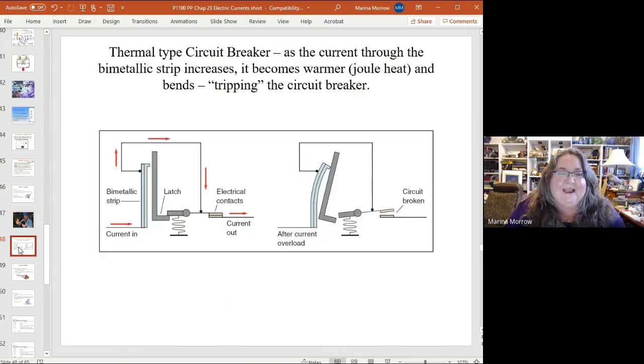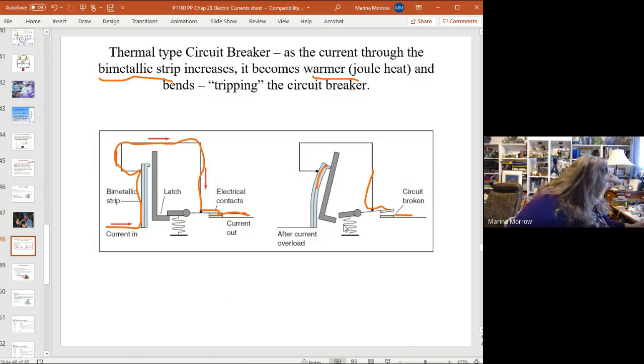So what's inside a circuit breaker? There are a couple of different types, but usually there's a bimetallic strip - remember we talked about those in the heat chapter - and they curve when they become warm, because too much electricity is flowing. The current flows in, through the bimetallic strip, up and around the latch, and out. When the current is overloaded, the bimetallic strip bends, that flips the latch, and now current can't travel - it's stuck, it's open, a broken circuit. That's how they work. You just have to push that latch back, and you can hear the little springing of the coils in there when you do that.